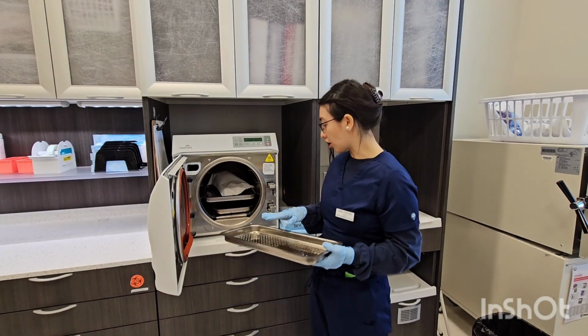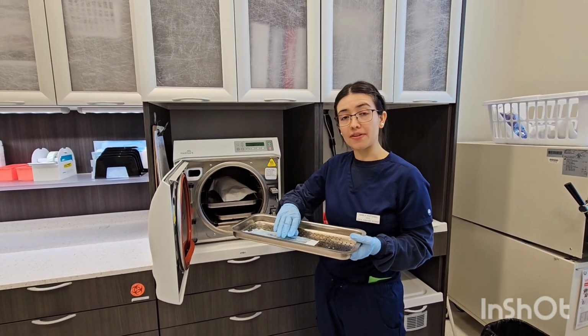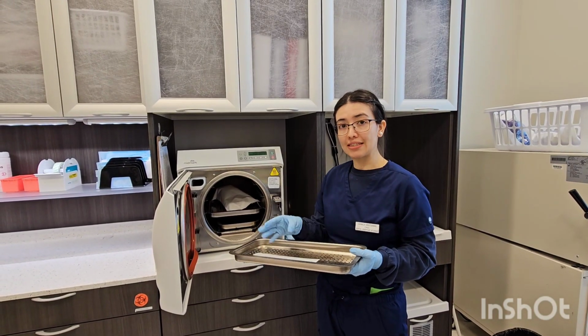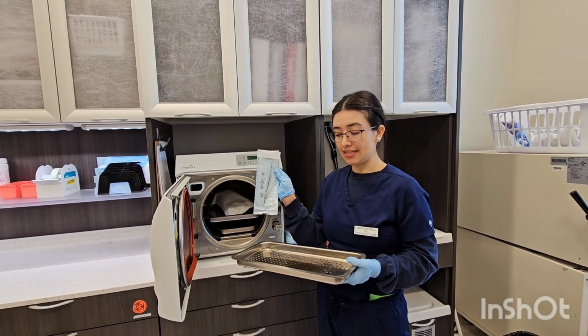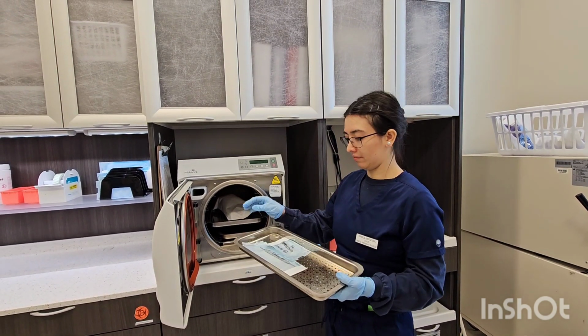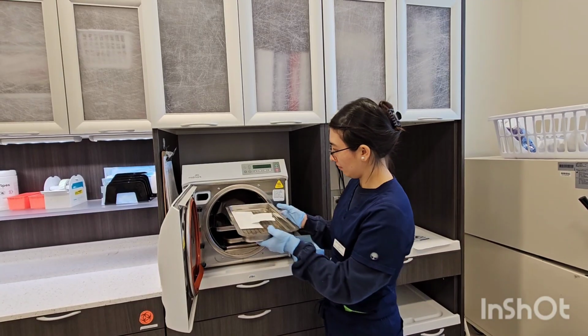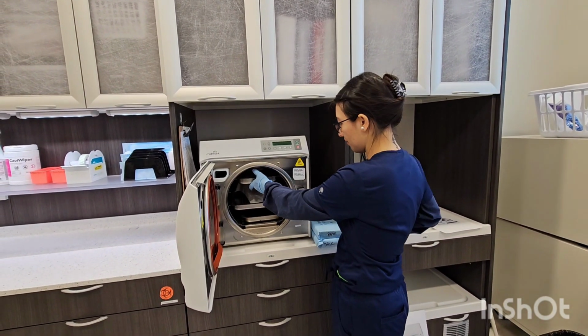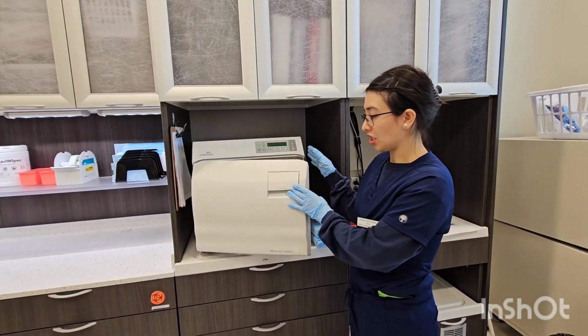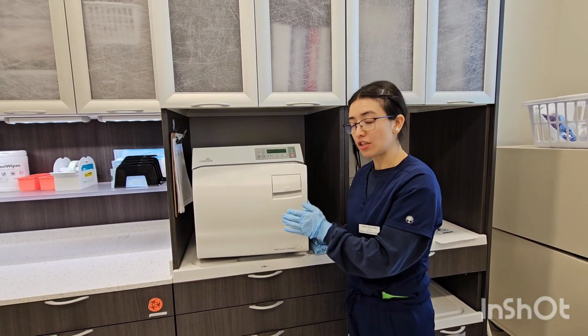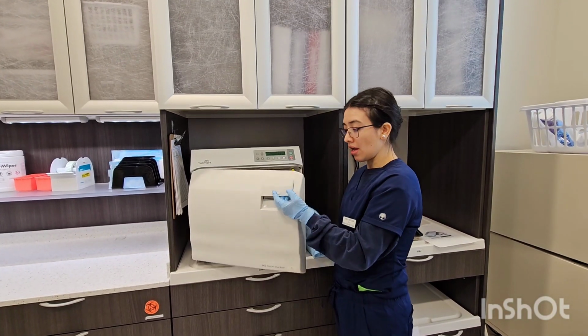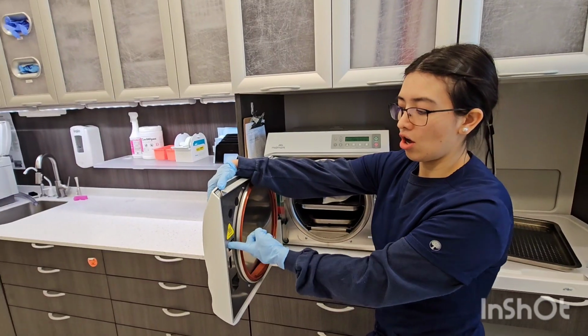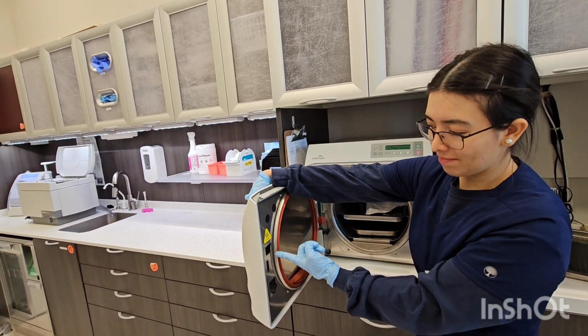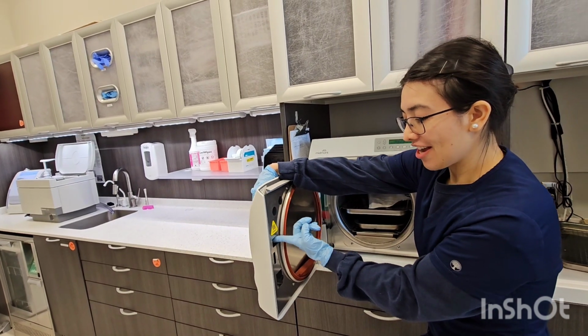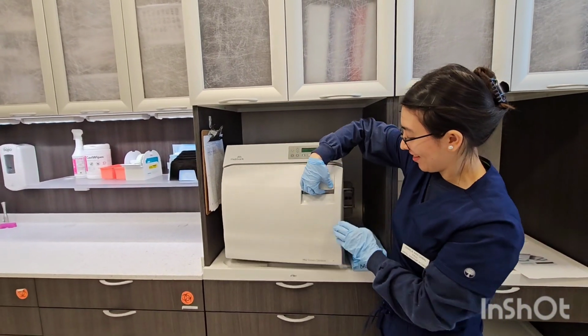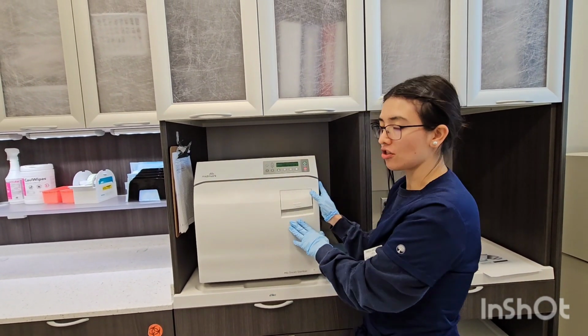It depends on the manufacturer's instructions. We are going to place the instruments facing up or facing down, so the steam goes through the package and steams the instrument. And we're going to go ahead and place them into the machine. Once we have placed everything into the machine, we have to make sure that it's completely sealed, and the way to do it is we have to lift this up, making sure that this is completely into this hole. We're going to push it down, close it, and make sure that it's completely sealed.